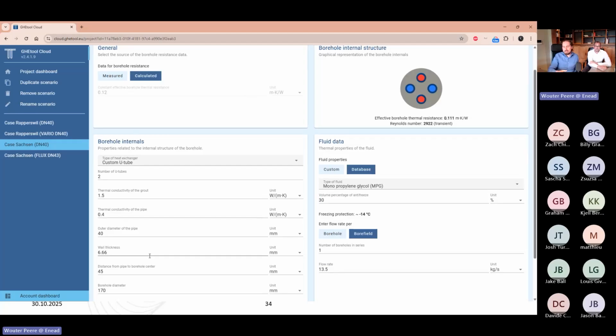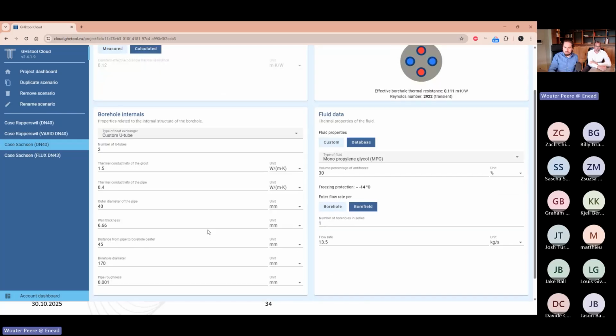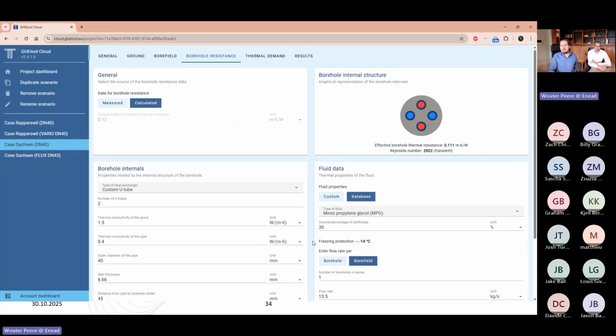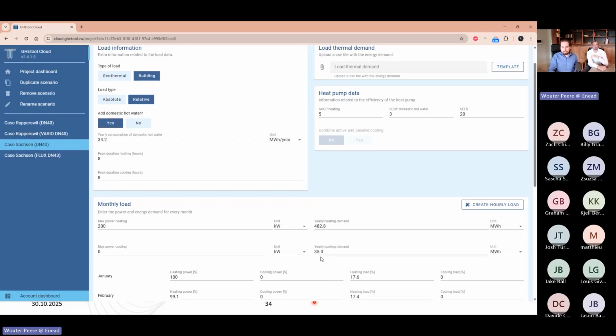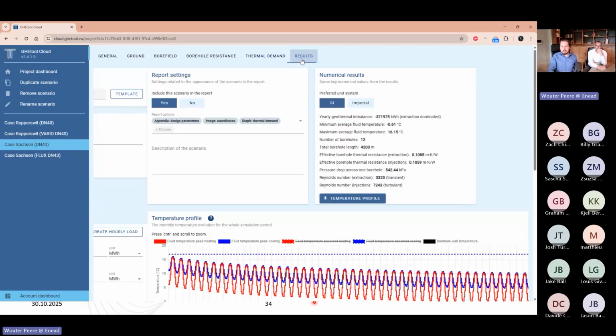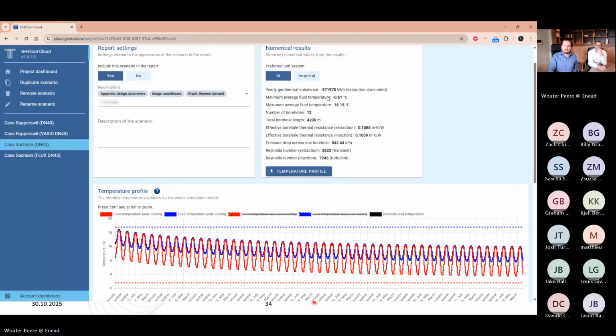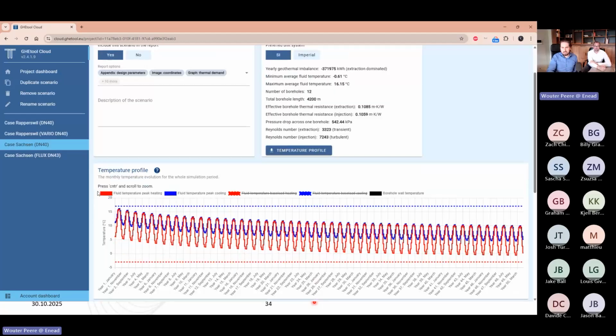If we would have had a PN32 DN40 probe, it would have had these parameters. So it's just a theoretical comparison. We have 30% monopropylene glycol and a flow rate. For our thermal demand, we have some yearly cooling for the regeneration. If we now go to our results, we see the following graph. Here we end up with a system that goes to minus 0.61 degrees Celsius, a borehole resistance just more than 0.1, and a pressure drop of 542 kPa, which is rather high.